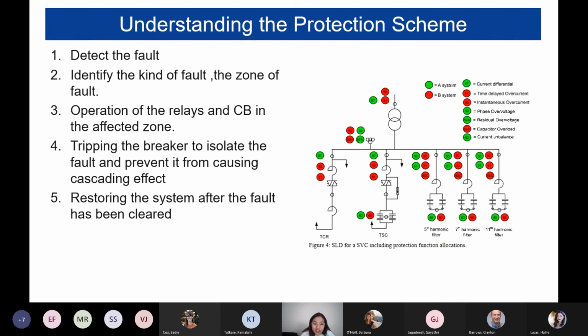Third, as I mentioned, operation of relays and CBs in the affected zone. Fourth, we need to closely monitor, and the alarming and acting system should be well communicated. It shouldn't happen that you raise an alarm and the system meant to isolate your equipment doesn't act on it. This could end up just feeding the fault with more current, so your tripping system needs to be accurate and agile at the same time.